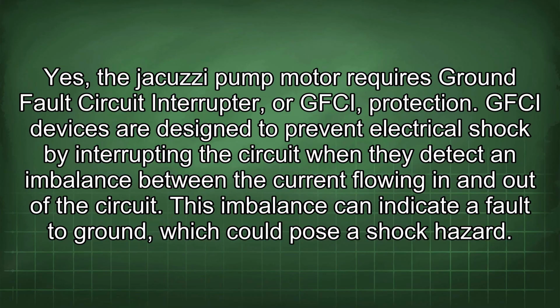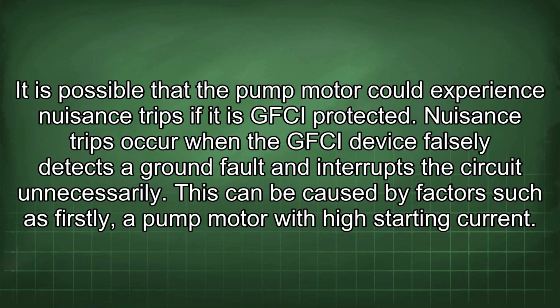Yes, the jacuzzi pump motor requires ground fault circuit interrupter, or GFCI, protection. GFCI devices are designed to prevent electrical shock by interrupting the circuit when they detect an imbalance between the current flowing in and out of the circuit. This imbalance can indicate a fault to ground, which could pose a shock hazard. It is possible that the pump motor could experience nuisance trips if it is GFCI protected. Nuisance trips occur when the GFCI device falsely detects a ground fault and interrupts the circuit unnecessarily.